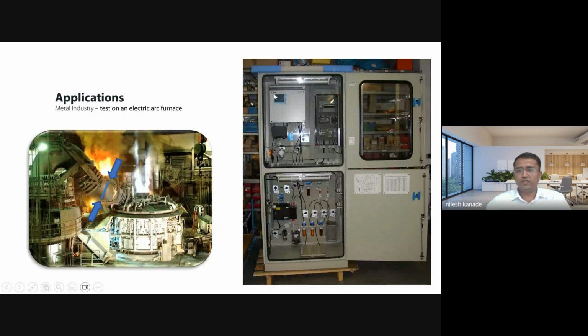the ABB make analyzer. To run this analyzer, a number of components are required, because the gases coming out from the process have very high temperature, high pressure, high flow and high moisture. Gas analyzers or sensors are not able to handle this high pressure, high temperature, high dust and high moisture. So to condition that sample, you need to design the gas analyzer sampling system according to your analyzer and sample requirements.